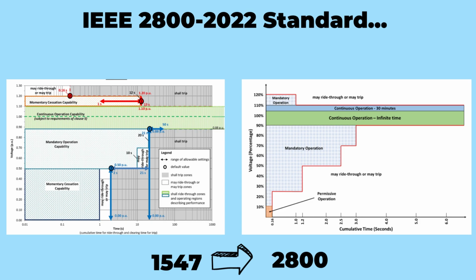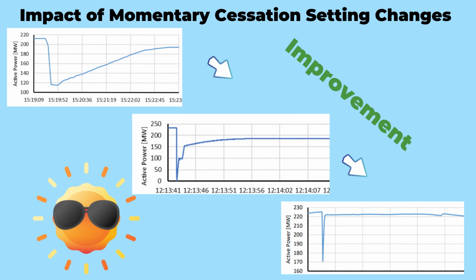But that's not all. The IEEE 2800 standard brings unprecedented clarity to the table. The requirements are now finely defined, providing a crystal-clear roadmap for IBRs to follow. No more guesswork or ambiguity, it's all about precision and efficiency. Now, let's explore the thrilling advancements observed through the adoption of setting changes in legacy inverters and the mandatory requirements laid out in the IEEE 2800 standard for new inverters.